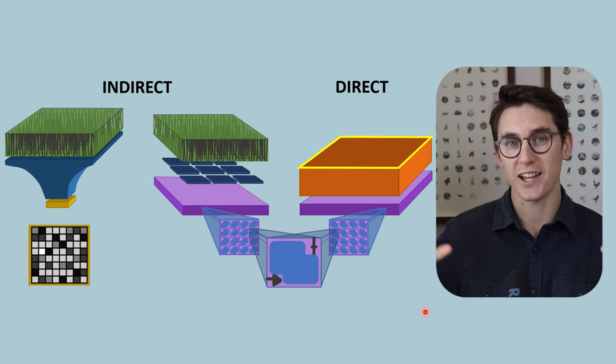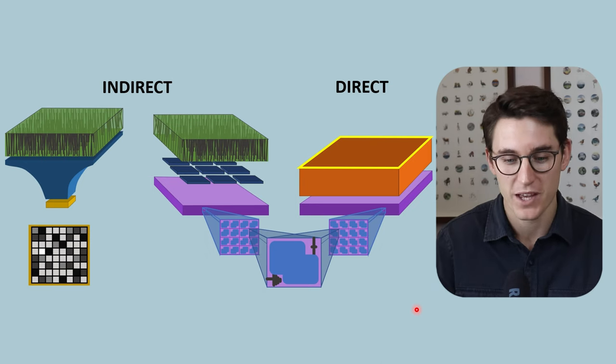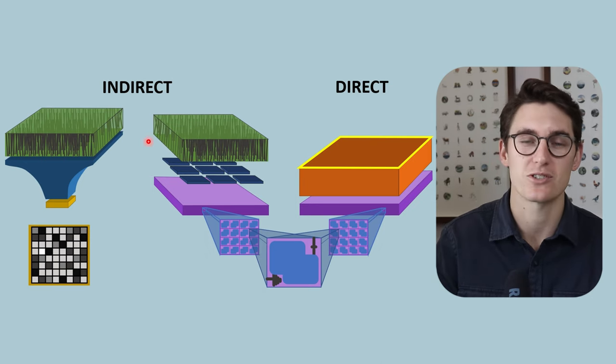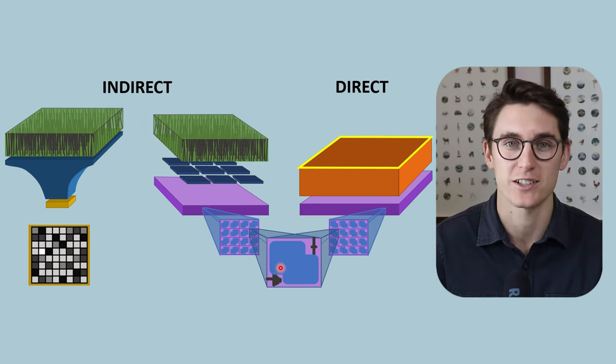Now we're going to look at our direct thin film transistor array, which doesn't require scintillation. It's still a digital radiography system, but we don't convert x-rays to light first. We convert x-ray energy directly into an electronic signal.